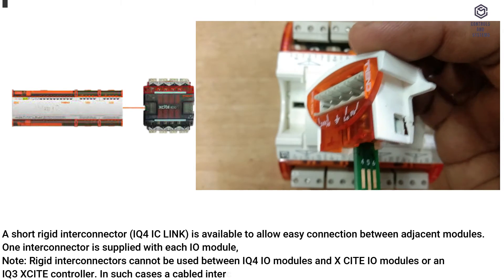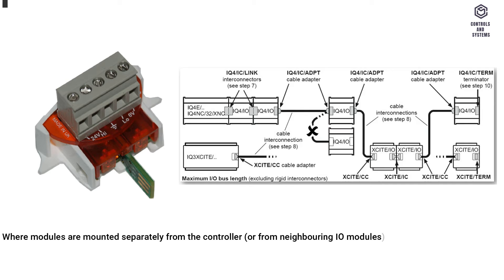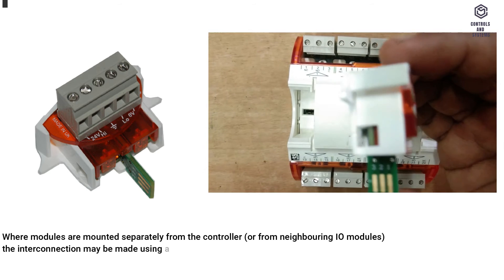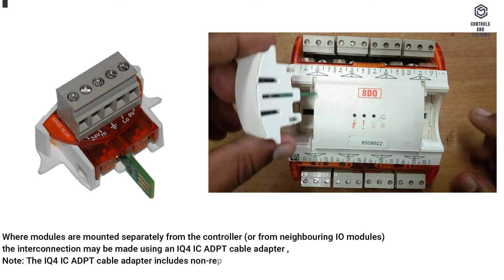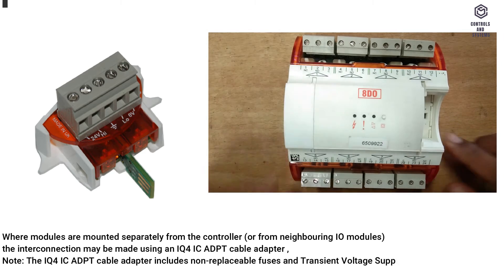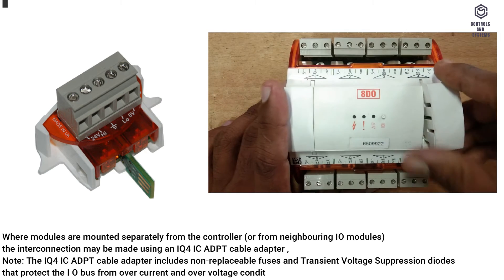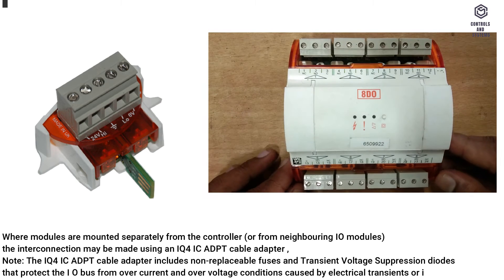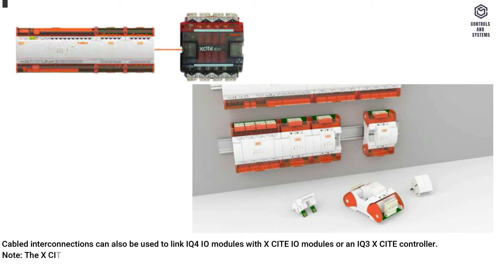Rigid interconnectors cannot be used between IQ4IO modules and X CITE IO modules or an IQ3 X CITE controller; in such cases a cabled interconnection must be used. Where modules are mounted separately from the controller or neighboring IO modules, the interconnection may be made using an IQ4ICADPT cable adapter. Note: the IQ4ICADPT cable adapter includes non-replaceable fuses and transient voltage suppression diodes that protect the I/O bus from overcurrent and overvoltage conditions caused by electrical transients or incorrect wiring.